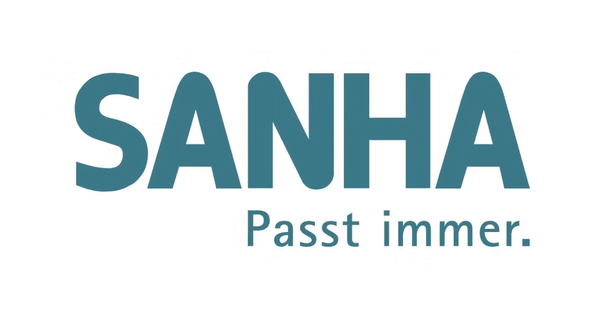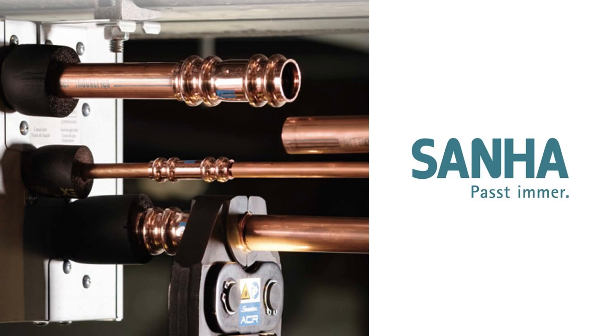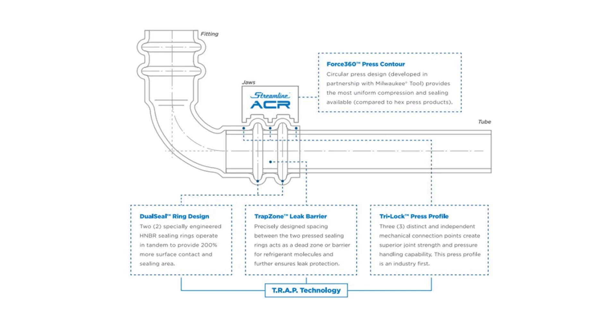Another German manufacturer, SANHA, now produces a Streamline ACR copper press system. The main feature of this product is that such connections can work at a pressure of up to 48 bar. For this, two sealing rings are placed in the socket of this fitting. Such fittings are compatible with refrigerants and many other gases.